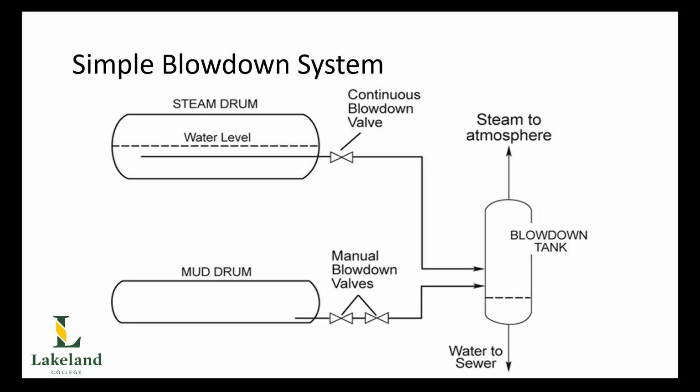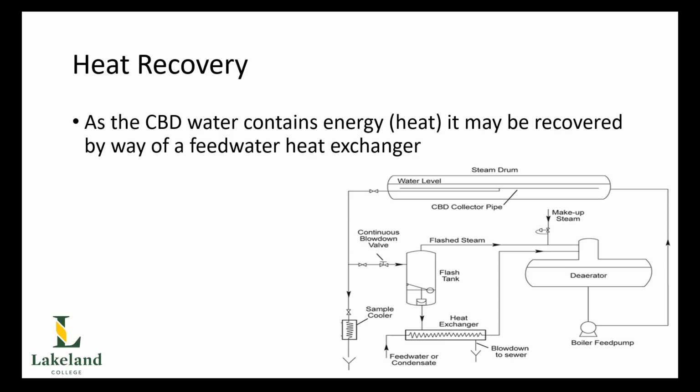Now, the purpose of the blowdown tank is simply to cool down the water to below 65 degrees before it gets discharged down to the sewer, as indicated, and it also is a place where it allows the water coming out at a high temperature to flash some steam off, and that steam can be flashed off to atmosphere. Now, of course, there are specific requirements for blowdown tanks, as outlined in B51, that we went over back in Chapter 5, and I do encourage you to review those in case you're a little bit rusty upon them.